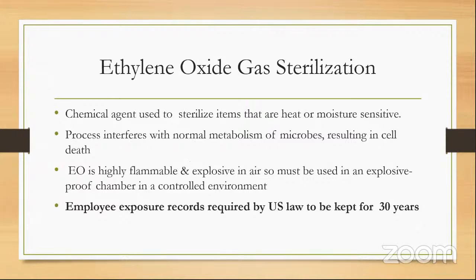So steam sterilization, I told you, is the most common physical sterilization method. Ethylene oxide gas sterilization is the most common chemical sterilization method that we use in this context. So ethylene oxide is a gas. It's a chemical agent and it's used to sterilize items that are heat or moisture sensitive. The process of ethylene oxide sterilization interferes with the normal metabolism of microorganisms and results in cell death. Ethylene oxide gas is highly flammable and explosive in air, so it must be used in an explosion-proof chamber in a controlled environment.